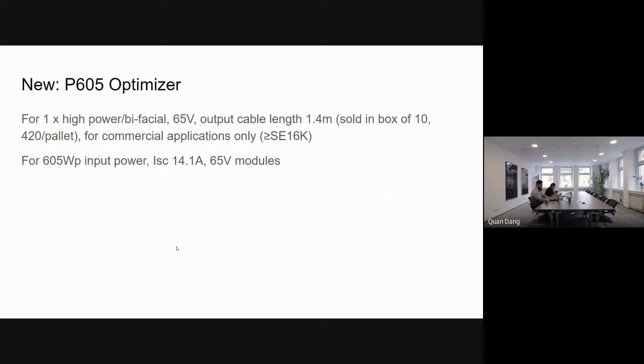Another news is P605. What is that? This P605 is a new optimizer which can be used for higher power, up to 605 watt modules, with input current 14.1 and voltage 65. Short description: the cells of the modules could be M12, because M12 usually has 13 amps output. However, very important - this one is not able to be used with residential inverters. You can use it for only one module and only for commercial application, meaning with inverters bigger than 16 kilowatts.